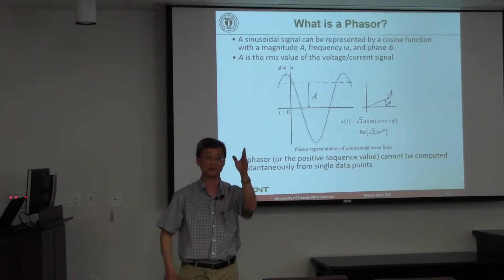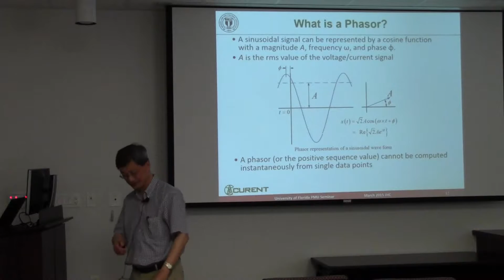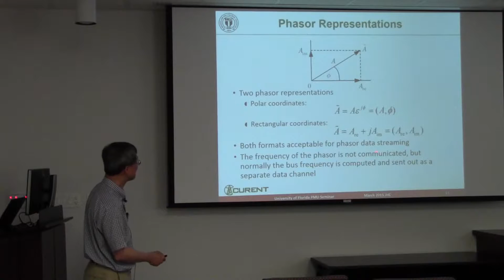One thing is that a phasor, or the positive sequence value of the phasor, cannot be computed instantaneously from single data points. You cannot take a snapshot of phase A, phase B, and phase C values — those are real values, not complex values. You cannot take those values and compute a phasor directly, that doesn't work. Also, a phasor can be represented by amplitude and phase, or by real part and imaginary part. Both are fine, both are acceptable for phasor streaming.